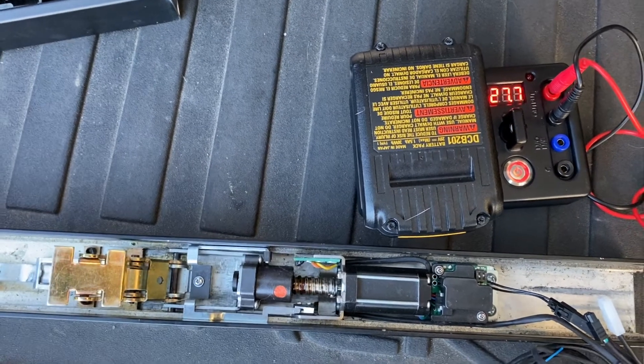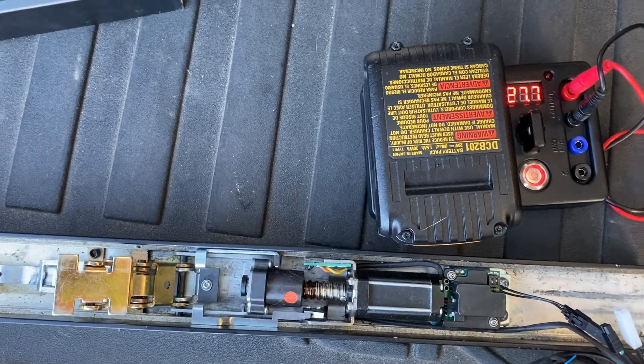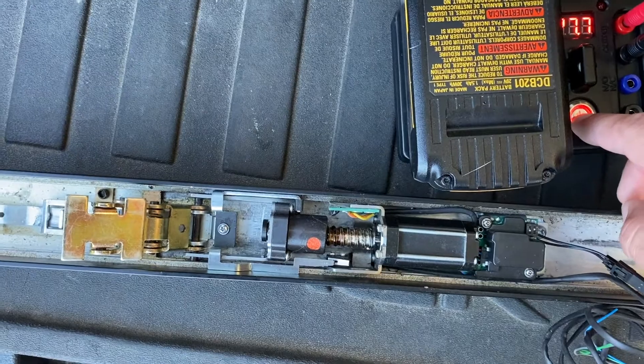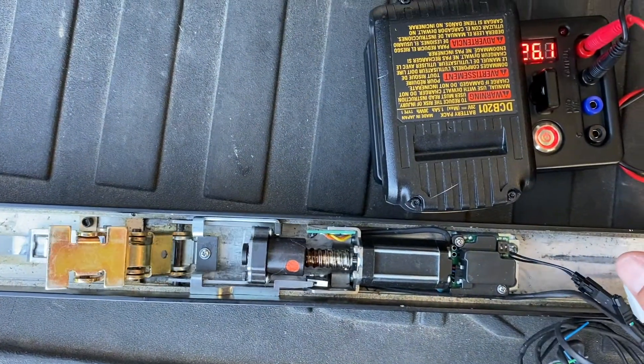Today I'm going to be showing you on the Adams Rite kit something that we discovered with the smaller motors and their sensitivity to higher voltage. You can see now with the CAT field tester that I have it at 27 volts, and it's firing and releasing almost like under voltage.